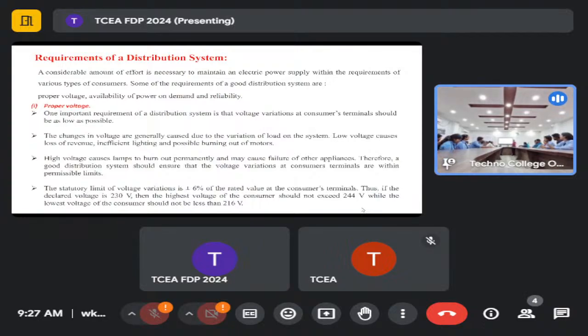I told you sometime that any distribution system requires proper regulation. What is regulation? Regulation means if you send X amount of power from one point to the other point, that X amount of power should be transferred with proper voltage level. In the process you will incur some voltage drops, but that must have a limit. As per Indian Electricity Rules, in the distribution sector, the voltage regulation is plus minus 6%. So if the declared voltage of a utility is 230, then it must be either 230 plus 6 or 230 minus 6.